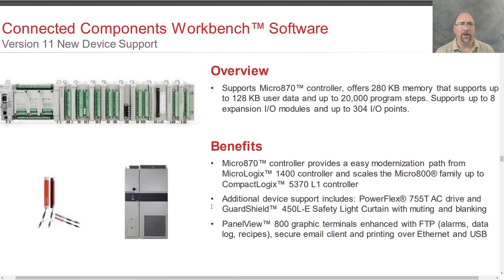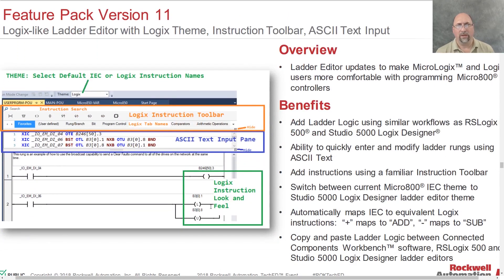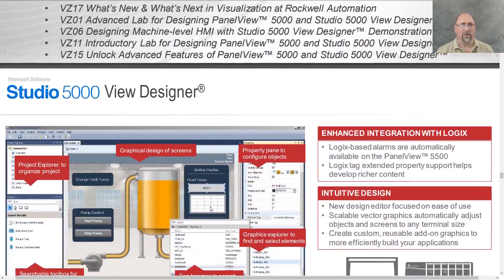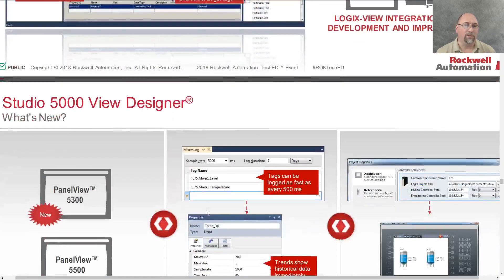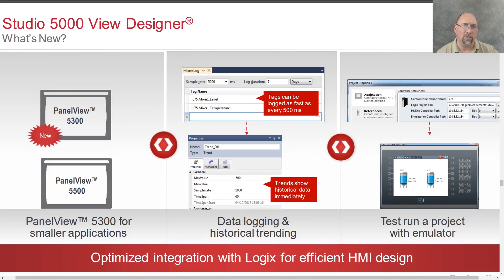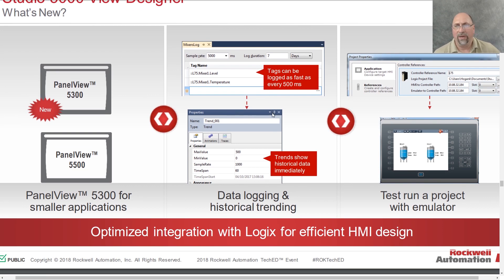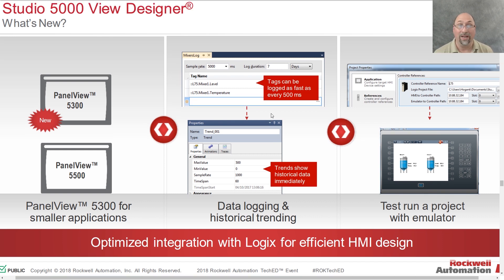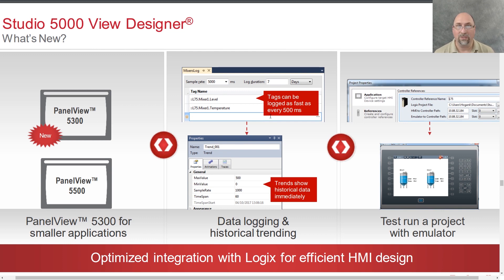I do want to get into the View Designer enhancements. In the previous hardware presentation we talked about the hardware, so I just want to touch on the tag logging - tags can now be logged as fast as every 500 milliseconds. That's extremely slow; I think it's 50 milliseconds in Panel View Plus 7, so I don't know what they're thinking. But at least it has data logging and historical trending now, since the product didn't even have that when it released. Test running a project is also new - that's huge. I just can't see myself trying this product without that feature.